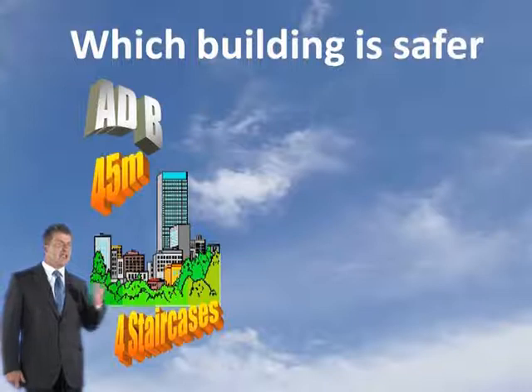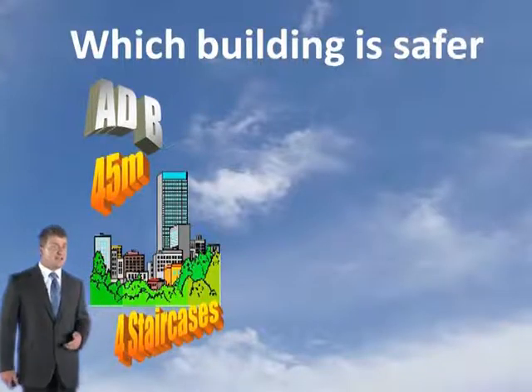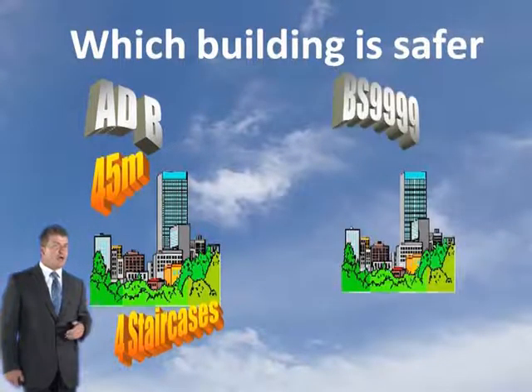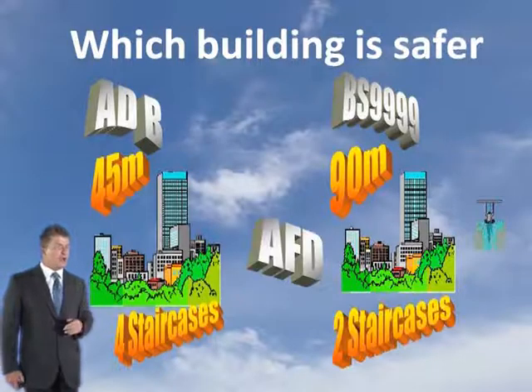ADB, 4 staircases, you've got 45 metres. BS 9999, you've got 90 metre travel distance, you've got early warning, and you've got sprinklers. Which building is actually safer? I think BS 9999 buildings are safer. Although you're extending the travel distance, you're taking into account putting in sprinklers. People don't die in sprinkler buildings. Go to America. It's fact. People don't die in sprinkler buildings. So by putting the sprinklers in, allowing you to change the risk profile and extend the travel distances, actually it's a safer building travelling further than ADB with 4 staircases.